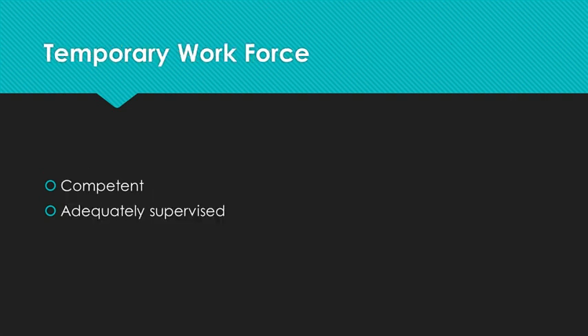Now, there's another piece to this as well. If you are moving personnel temporarily from one area to another, then actions must be taken to ensure that they're either competently trained to work in the new environment or adequately supervised to prevent an impact on the product. It is acceptable to move people around, but the company must ensure that they do not negatively impact the device, and they must have records to demonstrate how they ensured that there was no impact.